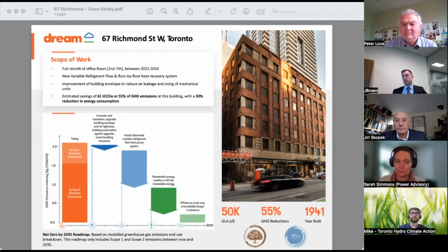In addition, at 67 Richmond we are installing an energy recovery ventilator, or ERV, to provide ventilation and precondition the fresh air as it cycles into the building. We also managed to complete some building envelope improvements, improving insulation and air tightness, which led to a 10% drop in HVAC sizing, saving us upfront equipment costs.